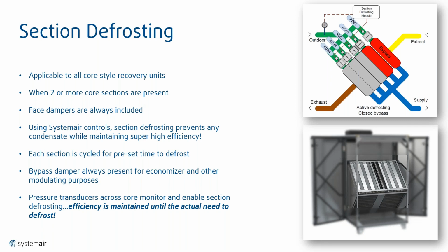Once we get to a section where we see that the frost is inhibiting the actual transfer of energy, we would then close that so that we can defrost, which means that the rest of the core still remains active. So you're continuously getting recovery on your core by dynamically defrosting. If you don't need to defrost that core, don't defrost that core, keep it going so that you can keep your energy recovery as high as possible. In the tests in the laboratories that we've had it in, we can run it down to about -13 Fahrenheit, so it's about -25 degrees Celsius. And that's where we're tapping out before you start needing supplemental heat to get that done.